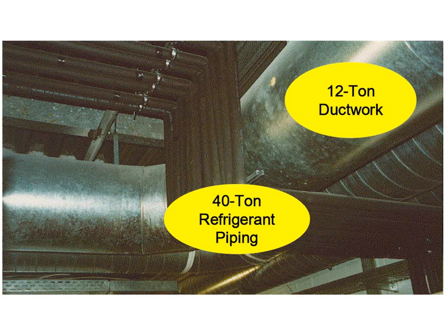And visually, it might look like this. This is a 40-ton refrigerant piping network sitting right next to a 12-ton ductwork system. And you can see that even though it's 3 times as many BTUs, it takes up a third of the space. So that's kind of the ratios we're looking at here. So it's really good for retrofitting systems where I want to move energy around the building without having to rip a lot of stuff open, and I might not have the space for a lot of ductwork.